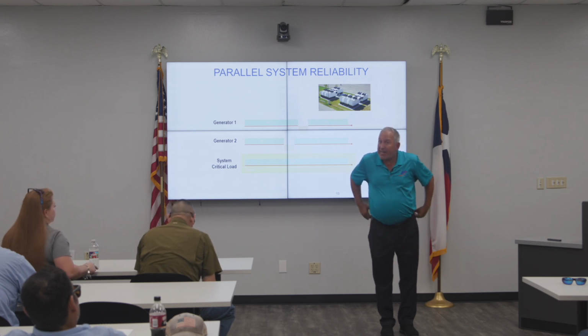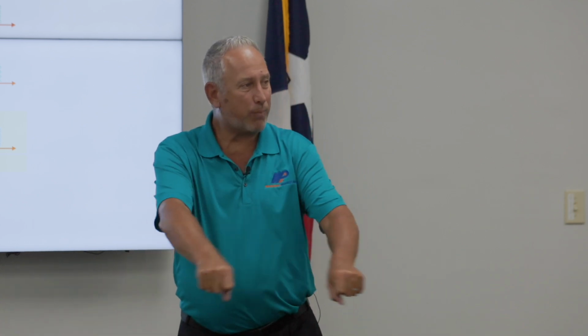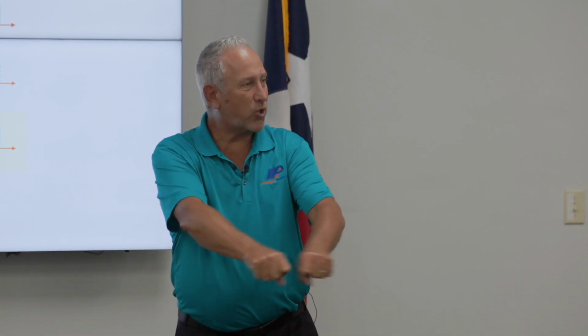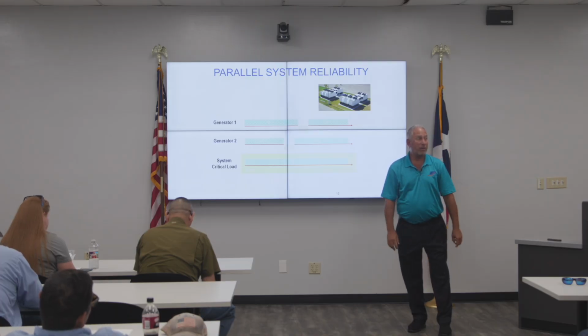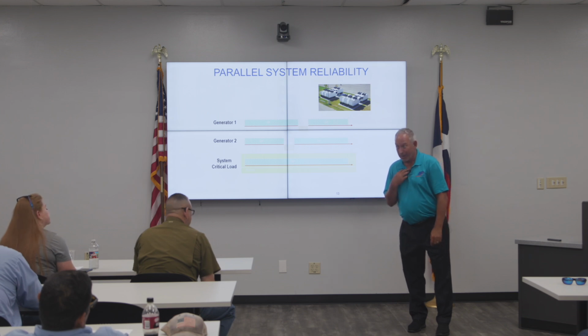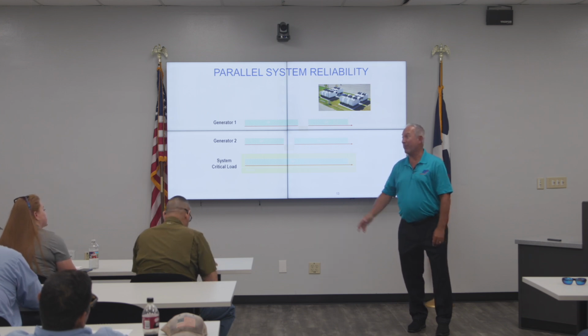So I can tell you today, that's all changed, that's all gone away. Now they put the controls for paralleling generators right on the generator, they can put a paralleling switch on it. So now you can plug a control wire between the two of them so they talk to each other and self-parallel. That's where it's gotten to today, so now I'm seeing parallel generators where I never thought I'd see it before.